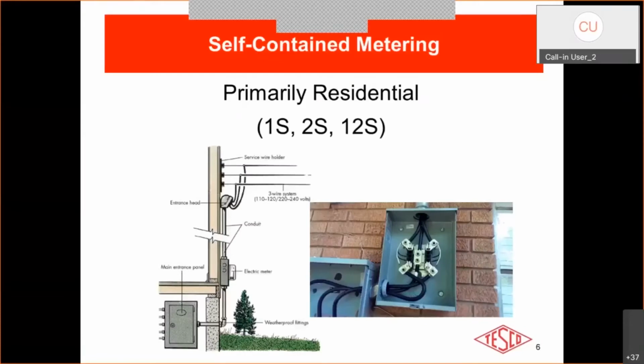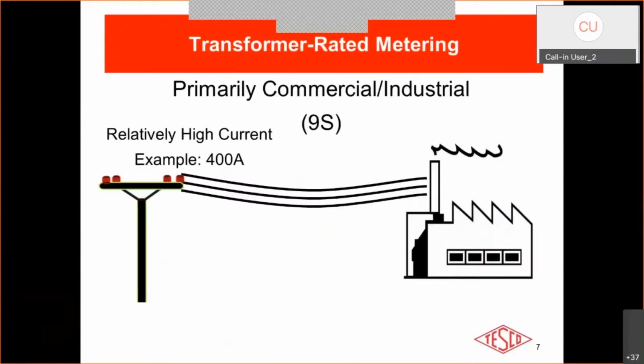Before we go further, here's a couple other pictures of a residential installation with the masthead, the service wires, the drop down to the electric meter, and on to the customer's load center. Alternatively, for your commercial and industrial customers and installations where you might have relatively high current flowing to the customer, you would use a transformer rated meter such as a 9S.